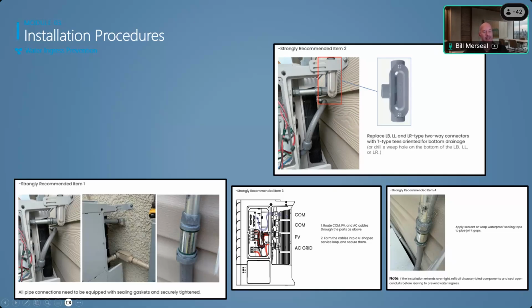Just do what you can to minimize any water intrusion opportunities. The other thing that's a good idea, for those who have done really well, is what we call almost like an electrical loop. Water will travel the path of least resistance, so if water does come in and you have almost like a drain loop, the water will settle on the bottom and drip without getting into your boards. Do all of these things and you won't have any issue with water. So I'd recommend, from a training standpoint, when training your team in the field, automatically train them to do the loop, make sure you're using seal-tight connectors, and have a way for that water to get out in case it does accumulate.